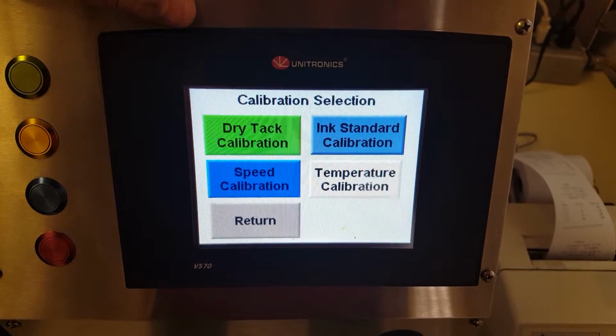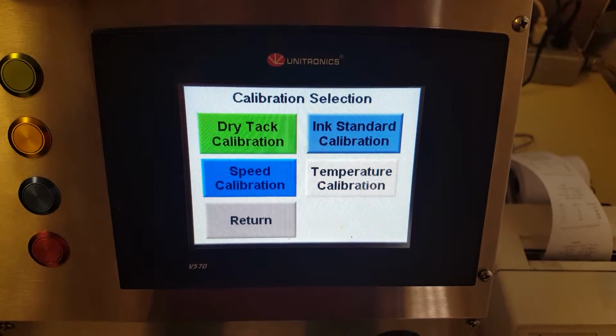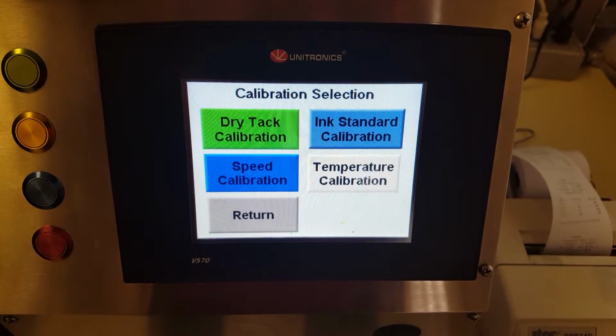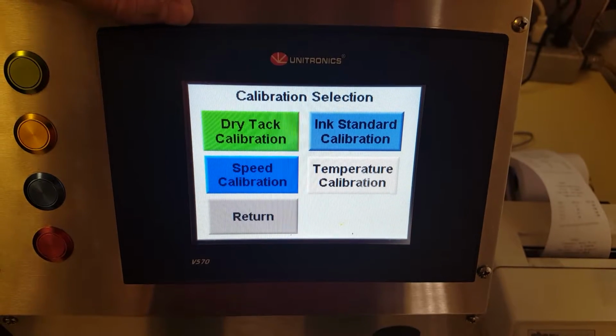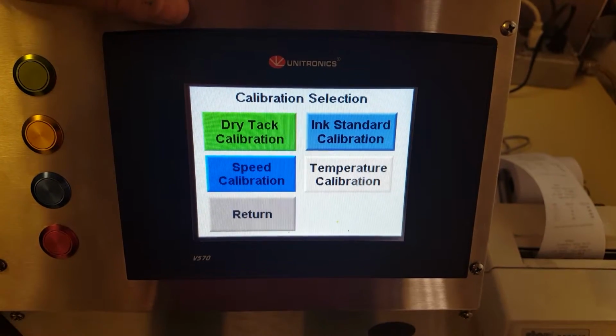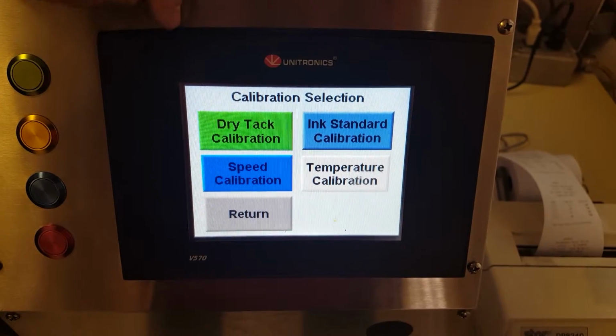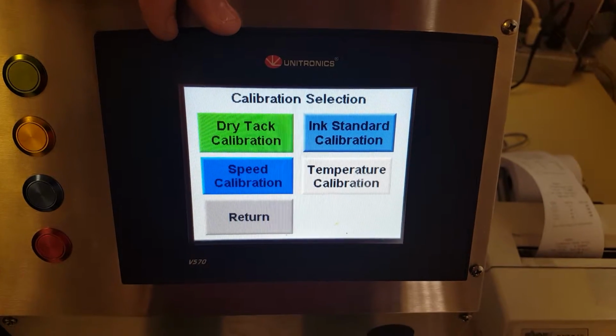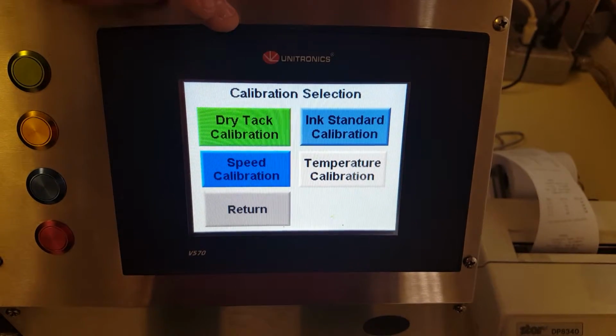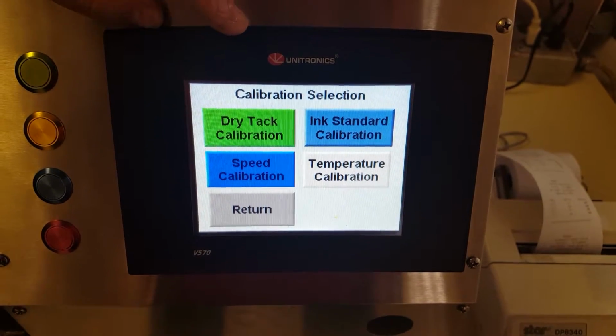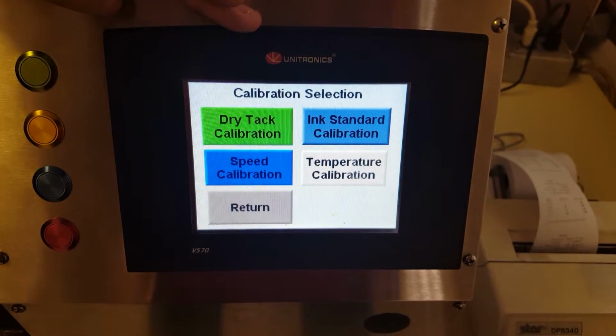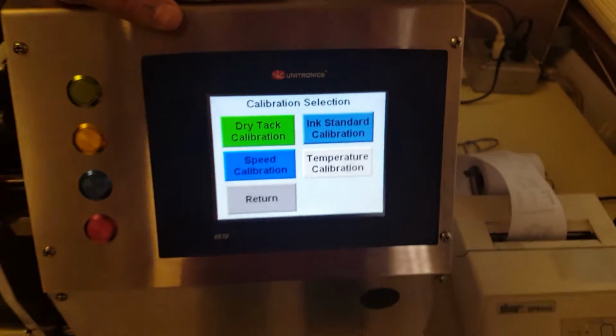And this machine is very stable. It can hold to around 5 RPM in either direction, and you usually won't see any issues with that changing at all. So with that being said, I'll move on to our tack calibrations here. The first one we're going to do is our dry tack calibration. Now I'm going to pan out so you can see the entire instrument here, and we'll go through these.